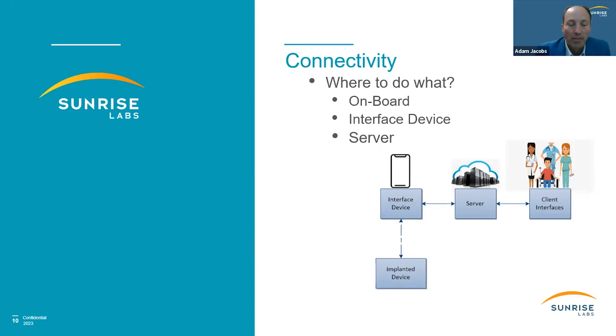So typically, for example in an ECG or an EEG, it's about 10 times more efficient to do the processing, say for beat-to-beat detection and some of the frequency work you would do in EEGs. It would take about 10 times more power to send it out. So you would do that on the device, which is one of the reasons why you want to get your signal processing as simple as possible.